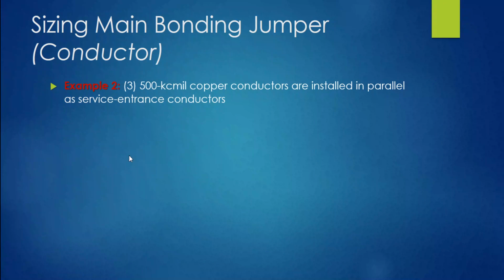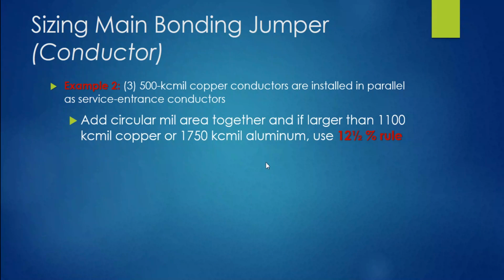All right, so now we've changed it up a little bit. We're bringing in 3 sets. So there's 3 parallel sets of 500 kcmil in the same application. And we'll see a graphic of that in a second so you can get a visual if you've never seen one before. Hopefully you have, but if you never have, we'll have a picture for that. So you've got 3 500 kcmil copper conductors installed in parallel as service entrance conductors. Okay, so now we're sizing that main bonding jumper.